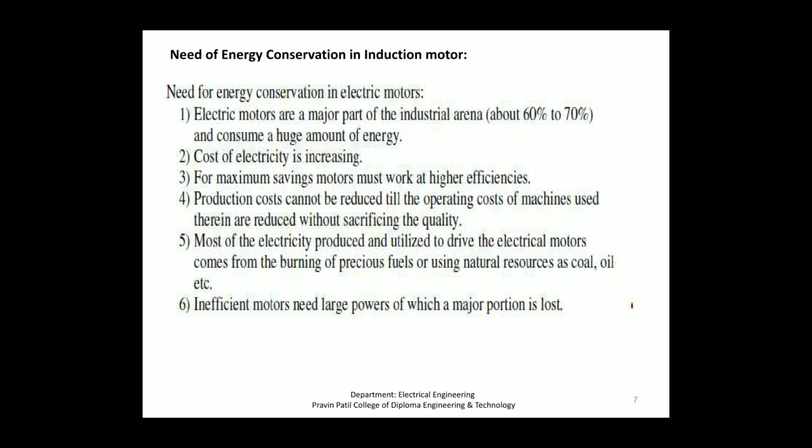The next is reducing underloading. The most common practice contributing to suboptimal motor efficiency is that of underloading. Underloading results in lower efficiency and power factor, and higher than necessary first cost for the motor and related control equipment. Original equipment manufacturers tend to use large safety factors in the motors they select.